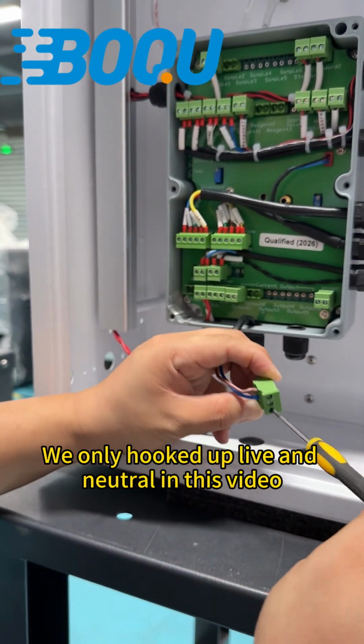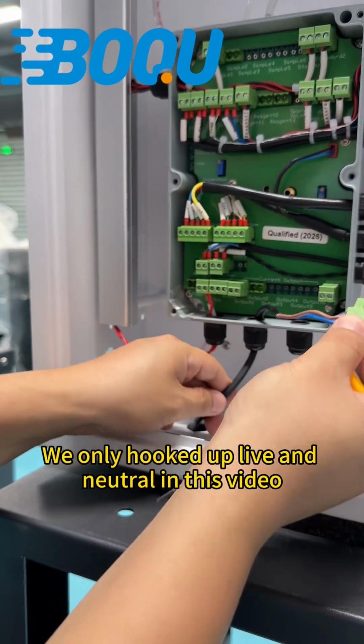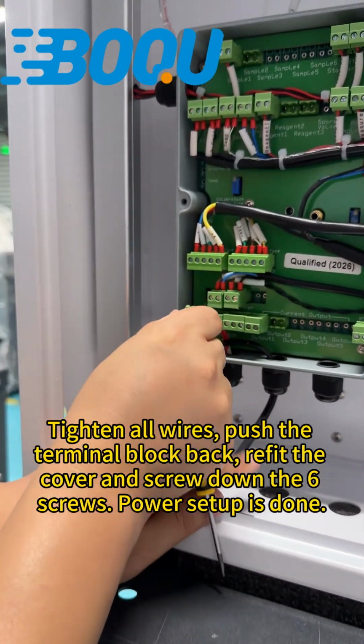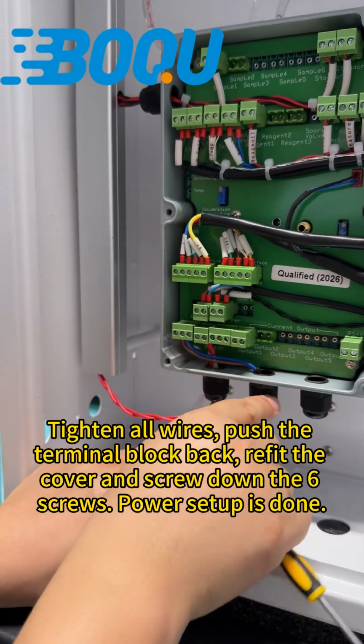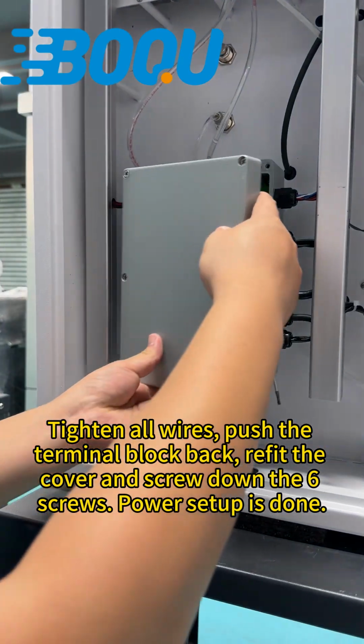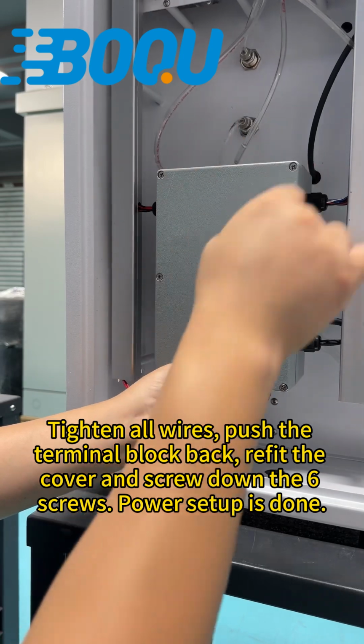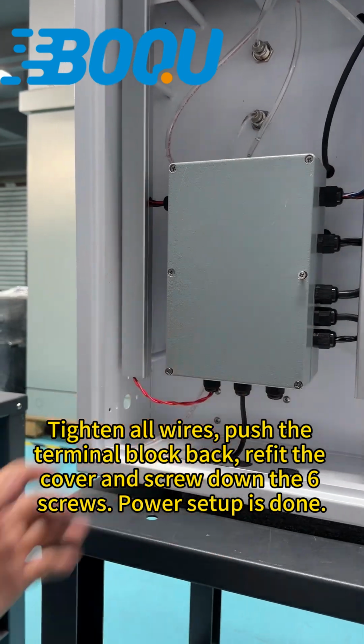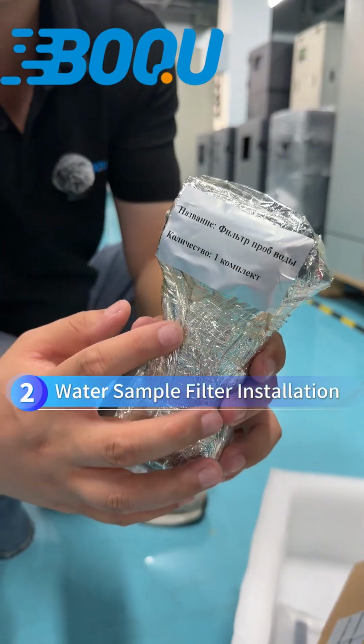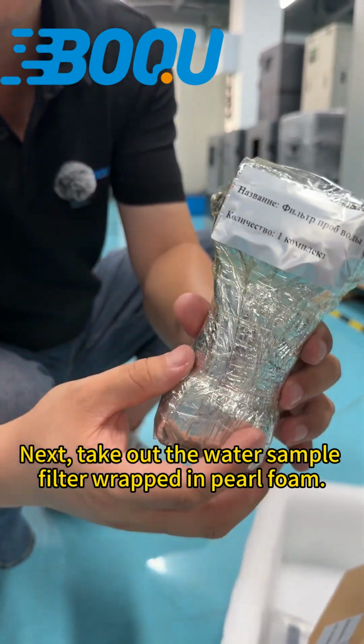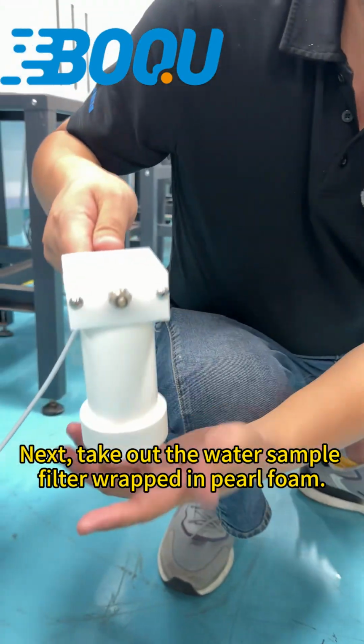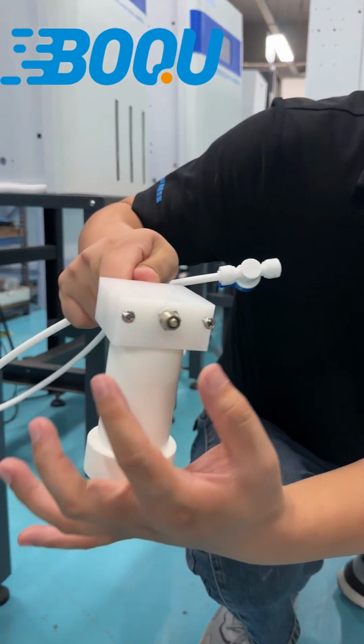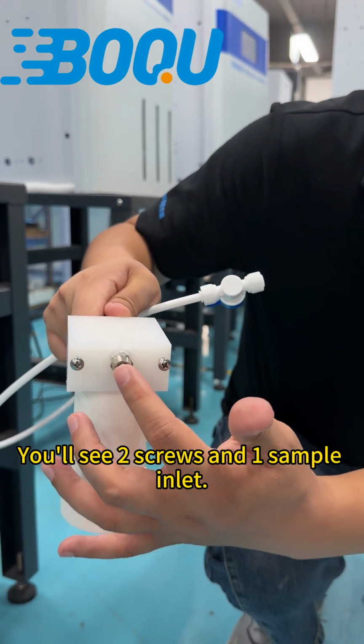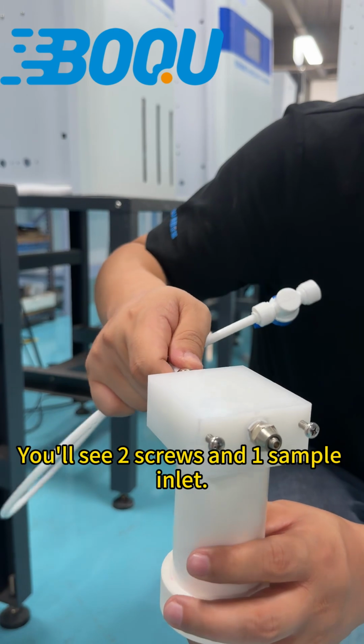We only hooked up live and neutral in this video. Tighten all wires. Push the terminal block back. Refit the cover and screw down the 6 screws. Power setup is done. Water sample filter installation. Next, take out the water sample filter wrapped in pearl foam. You'll see 2 screws and 1 sample inlet.